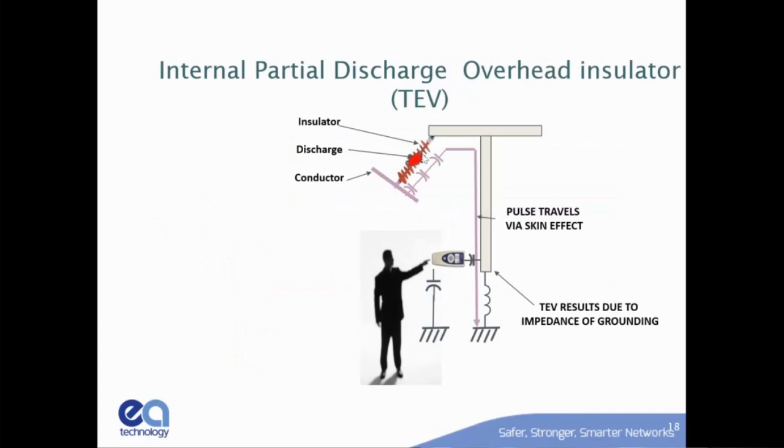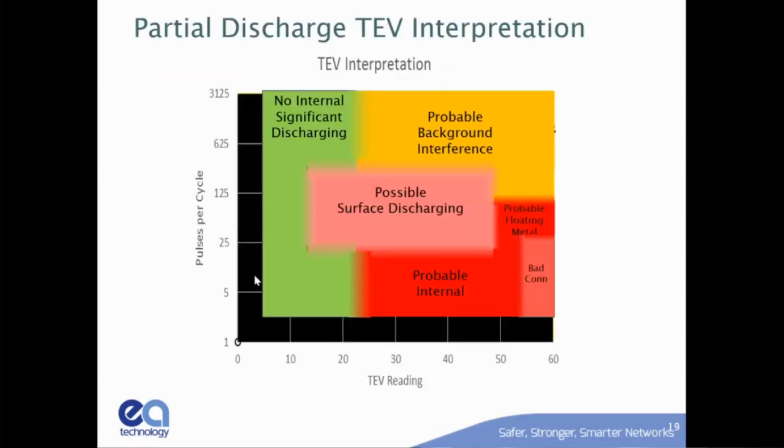If you're doing any outside work where you have an insulator and that insulator is grounded, a metal pole or a ground wire, maybe coming off a Viper sectionalizer or something like that, you can put the sensor right on that wire going down the pole, or put it on the pole itself. There's going to be an impedance between that pole and ground, and you can see the voltage that is on the actual ground wire. So you can use it for overhead stuff.